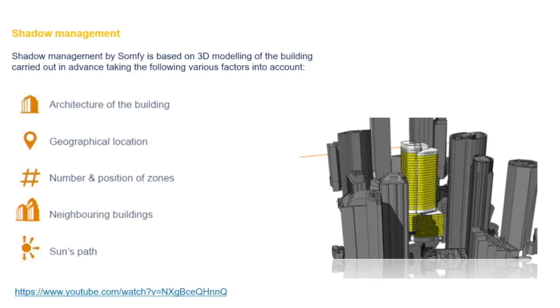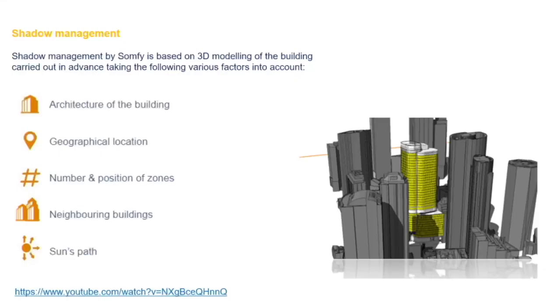We run a highly computer-intensive process where we model the sun across the building in 10 or 15 minute increments throughout the whole day, every day of the year. We look at each individual zone and multiple areas within it to determine exactly where the shadow is and whether any sun is hitting that part of the building. This lets us be very accurate about whether there's shadow there or not. It's a fantastically sophisticated system, but it works very well.